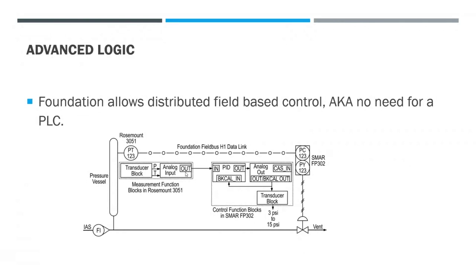Advanced logic associated with Foundation, of course. Still talking about how it allows that distributed field-based control, where we can do PID measurements in our analog devices, our pressure transmitter in this case, and our pressure controller or our valve here. We can do this outside of the PLC system, so no need for a PLC. I don't know of any applications that use it, but it's capable of it.